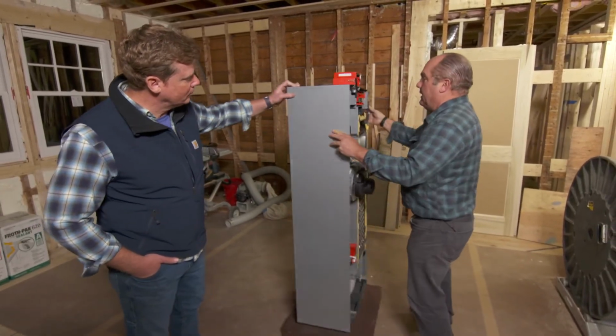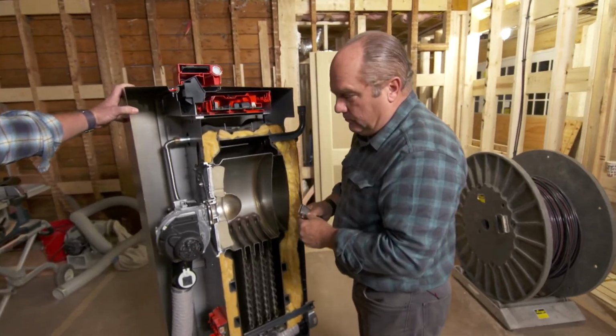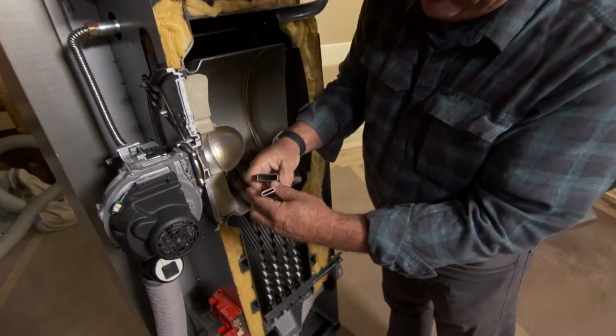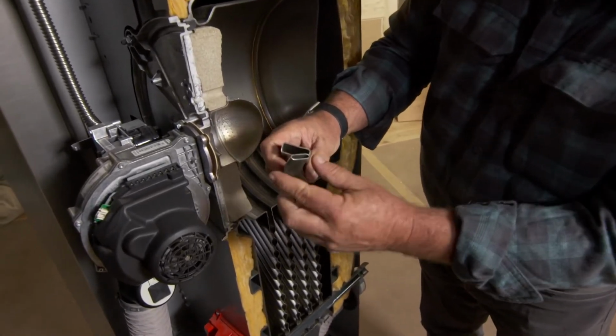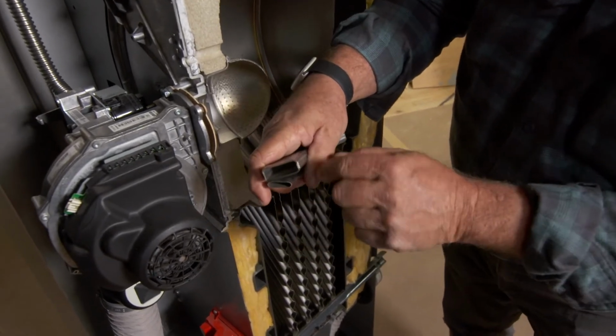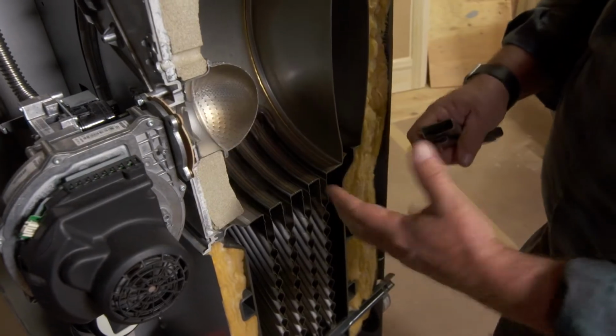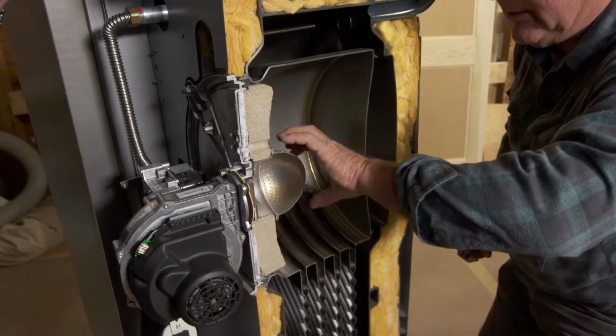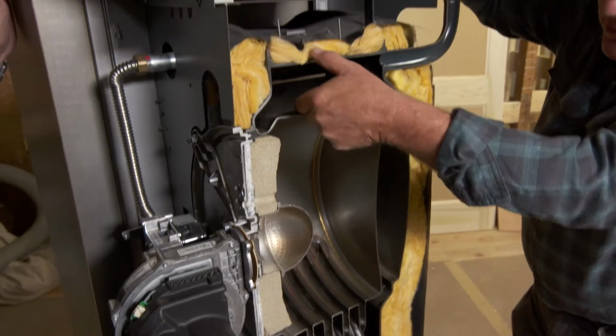It helps to understand. When these wall-hung boilers first came out, the heat exchangers had relatively small water content. This was one and this was another, and these would be stacked together and the flame would come through. And that's the full volume of water you had in either of those. And so with this, you can see a burner right here. The burner comes with this beautiful flame that will just modulate and change according to how cold it is outside. But this is how much water content.